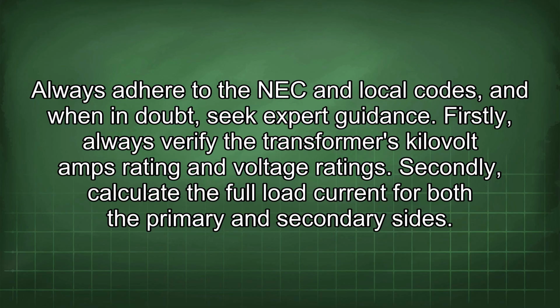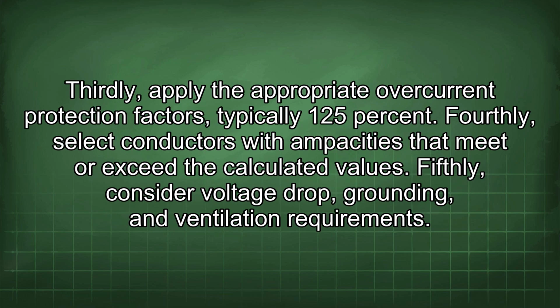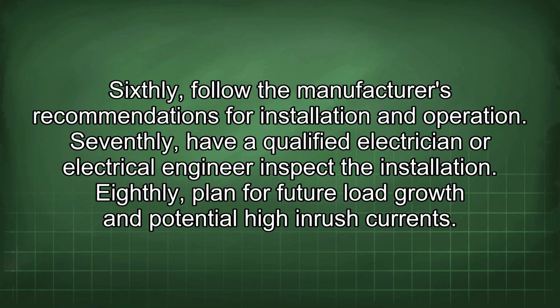Firstly, always verify the transformer's kilovolt amps rating and voltage ratings. Secondly, calculate the full load current for both the primary and secondary sides. Thirdly, apply the appropriate overcurrent protection factors, typically 125%. Fourthly, select conductors with ampacities that meet or exceed the calculated values. Fifthly, consider voltage drop, grounding, and ventilation requirements. Sixthly, follow the manufacturer's recommendations for installation and operation.